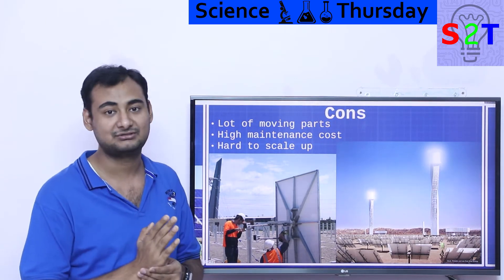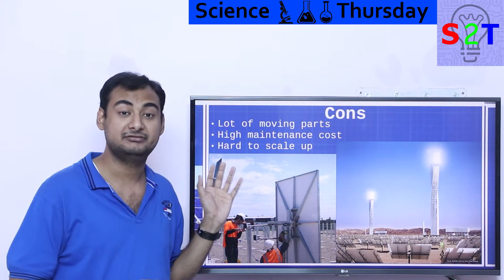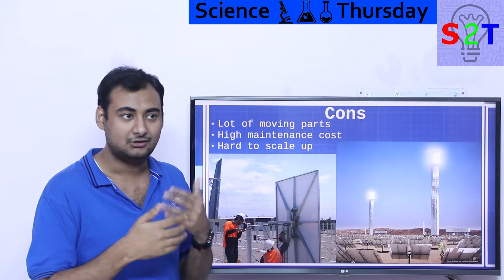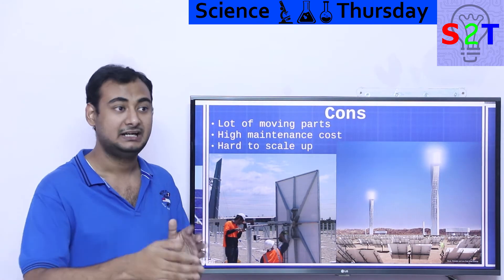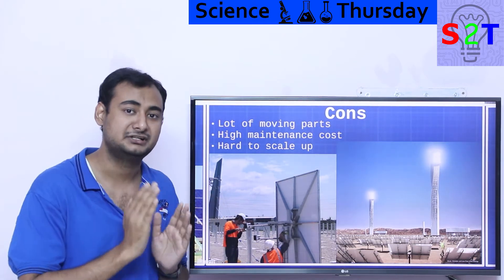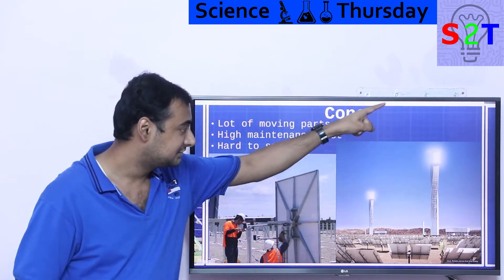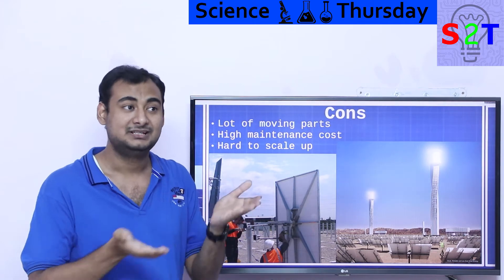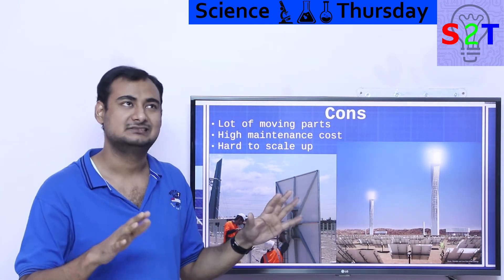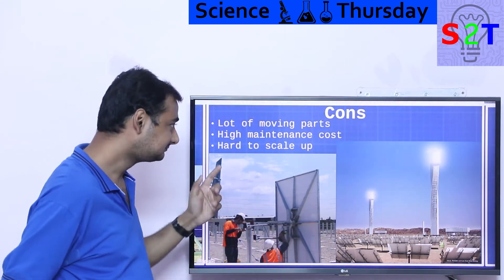You have to maintain it constantly, and anyone who has worked with bearings knows they're very sensitive — especially in a desert environment. They are also very hard to scale up. With solar PV, you buy an inverter that converts DC to AC and sell it to the grid. Want to add more capacity? Just buy another inverter — there are string inverters that let you chain up to hundreds of megawatts easily. With solar thermal, you have to make sure the thermal plant is sized correctly on day one. Because of how steam works, it won't start up below a certain temperature threshold, so you can't easily scale it from day one.